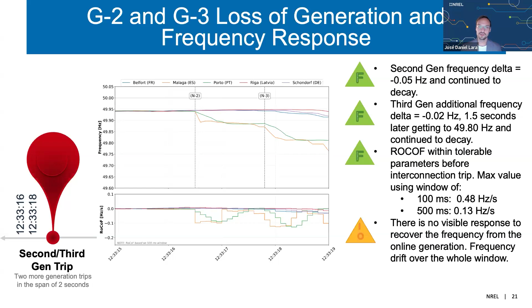And then this is where the plots start to get really interesting, because the data showed us that after this second loss of generation in Badajoz, the voltage starts to rise, and the operator starts to, you see this voltage rise, then we lost a second unit again in Badajoz, and the voltages continue to rise, the frequency continues to drop, and at some point we actually lose the generation of the 6 trips that happened, right? There's an extra generation loss here, and we could continue to see the voltages continue to creep up and the frequency to drop. So at this point, there's a reversal of the flow with France, where the system in Spain continues to trigger voltage trips, and the loss of power generation reverses the import to export, right? Sorry, the export to import.